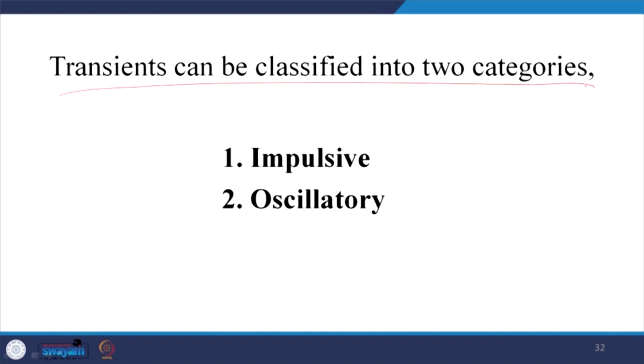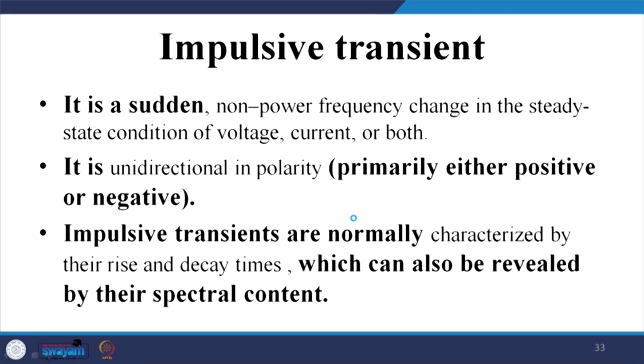Now, transients can be classified into two categories: one is impulsive, another is oscillatory. What is an impulsive transient? It is a sudden non-power-frequency change, mind you it can be any hertz, in the steady state condition of voltage, current or both. It is unidirectional in polarity, generally either positive or negative. Impulsive transients are normally characterized by their rise and decay times, which can also be revealed by their spectral content. So, you require a spectral analysis and you can find it out.